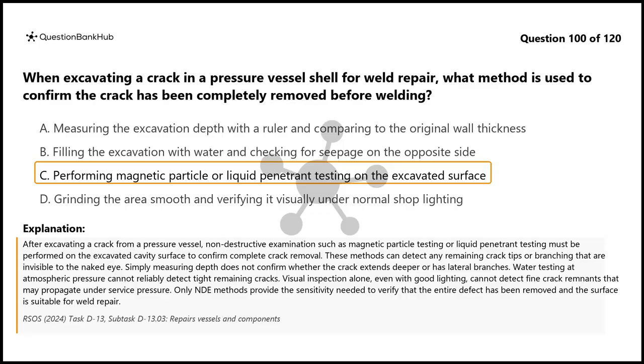Water testing at atmospheric pressure cannot reliably detect tight remaining cracks. Visual inspection alone, even with good lighting, cannot detect fine crack remnants that may propagate under service pressure. Only NDE methods provide the sensitivity needed to verify that the entire defect has been removed and the surface is suitable for weld repair.